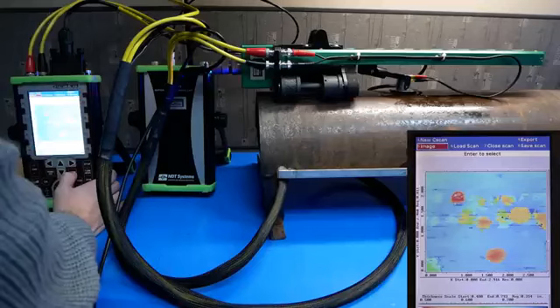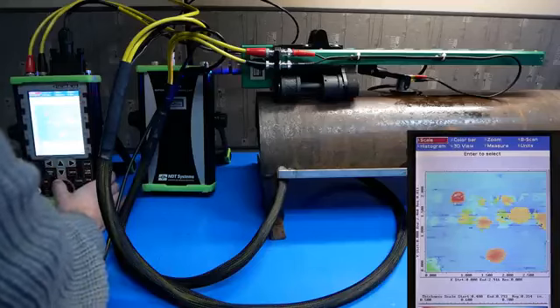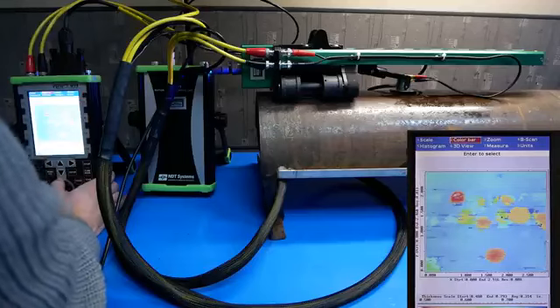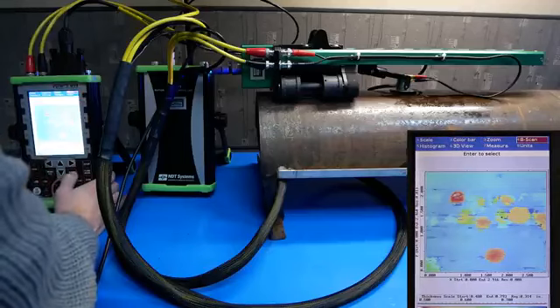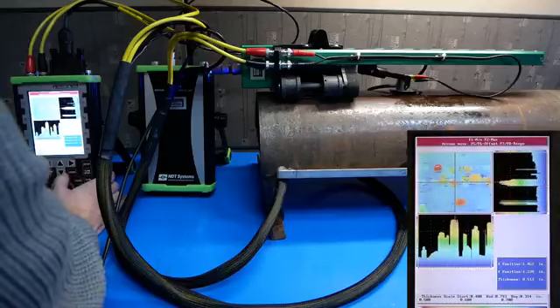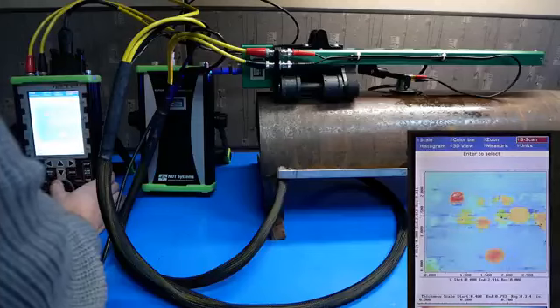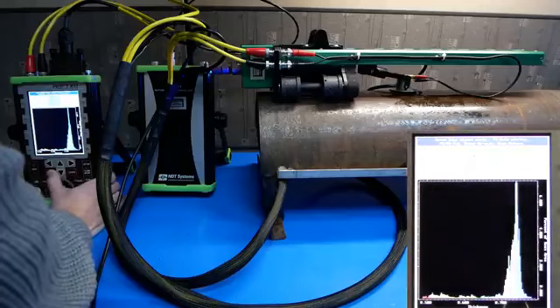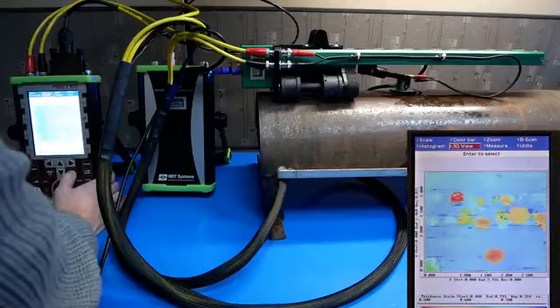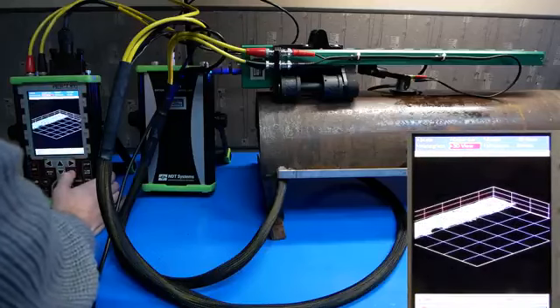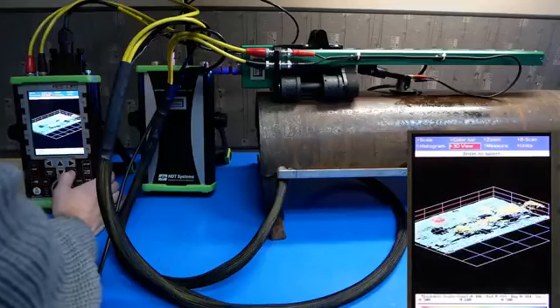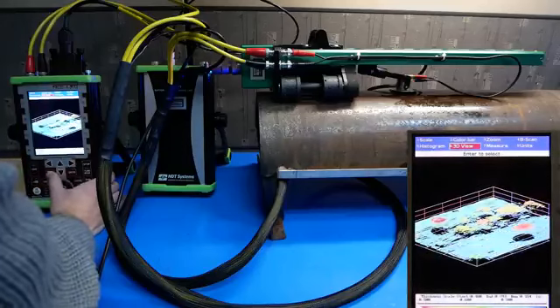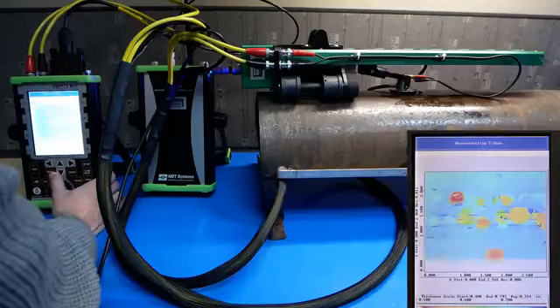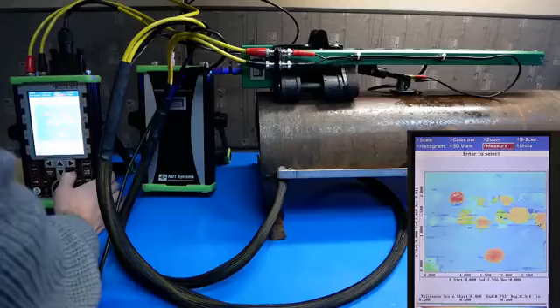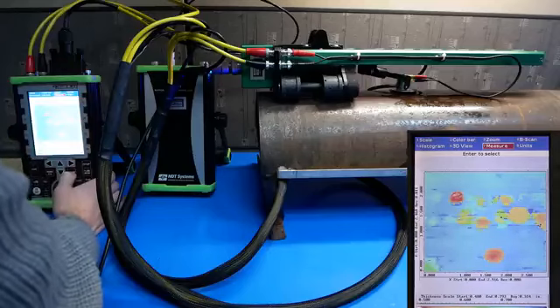We can also take a look at the image and manipulate it in a variety of ways by going to the Image tab. We can change the scale, the color bar properties, we can zoom in, we can take a look at a B scan generated from the C scan data. We can take a look at a histogram of commonly measured values. We can populate the data in a 3D view. And we can measure any particular spot to find a thickness at a designated spot.